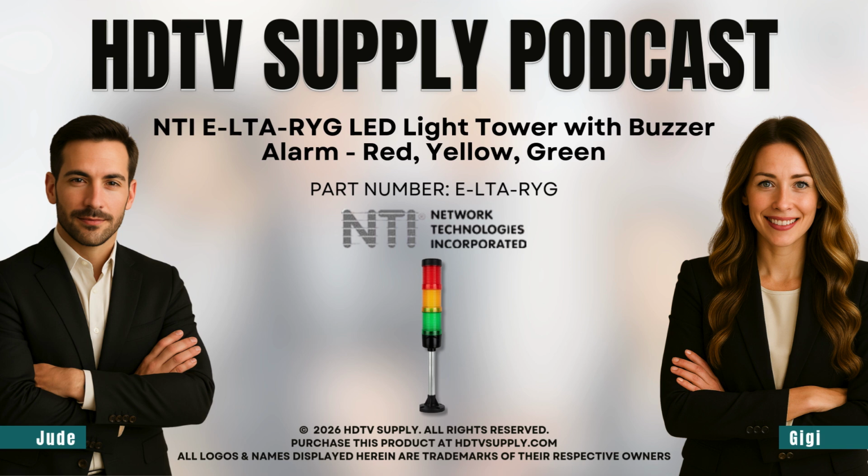Such a key point. I also looked into the durability because these things live in pretty harsh places. It's rated IP53, ingress protection. So the 5 means it's protected against dust, which is essential for a factory floor. Yeah, the 3 means it can handle spraying water. So a pipe bursts or someone's hosing down the floor, the alarm itself won't die. And the lifespan. The MTBF, or mean time between failures, is listed at 50,000 hours.